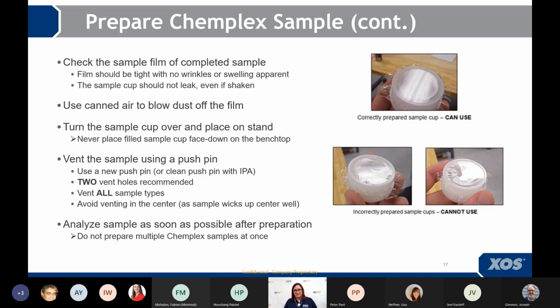And when you go to vent the sample, here's one that not everybody knows. Those Chemplex cups have that nice little divot or well in the center of the cup. And you think that's exactly where I want to vent it. But actually, we recommend to not vent there. The reason for this is simple: when the well touches the sample, the sample will wick up that well. And if you vent there, you will have more sample come up and settle on the top of the cup. So you're actually going to vent off center with your push pin.